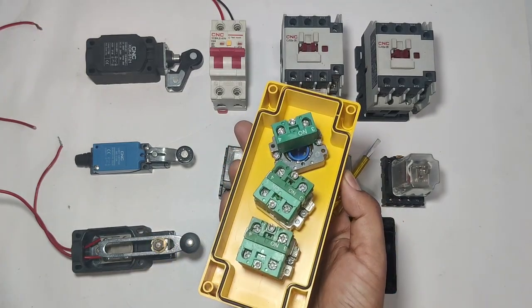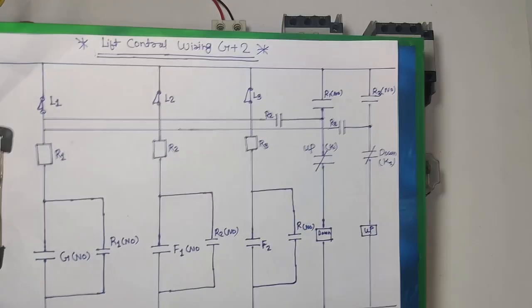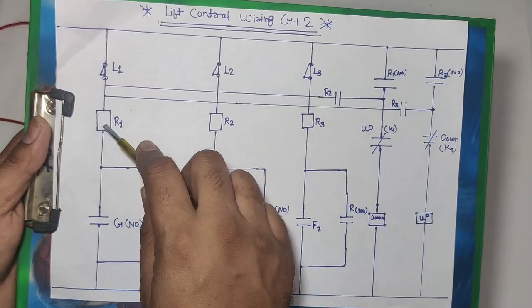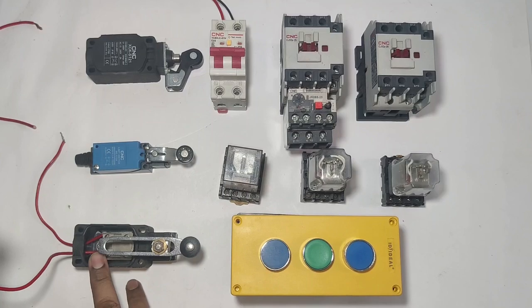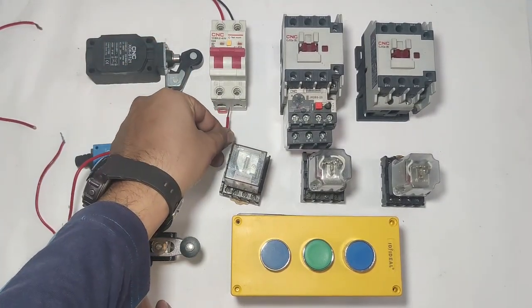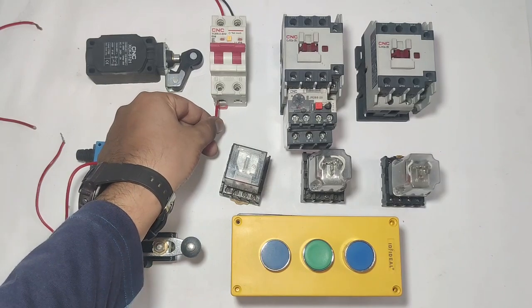Neutral connects first to the ground floor push button NO element. When this push button is pressed, neutral comes into the relay coil and the relay operates. For the R1 relay, line connects in the L1 limit switch NC point and the NC output connects to relay pin 10.